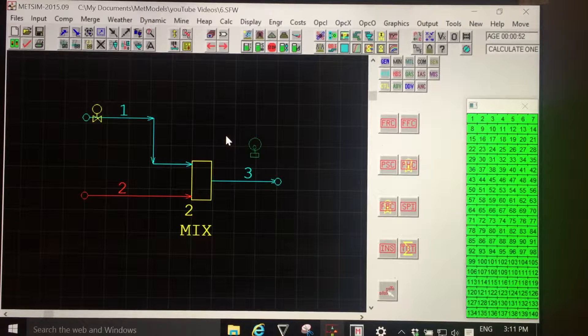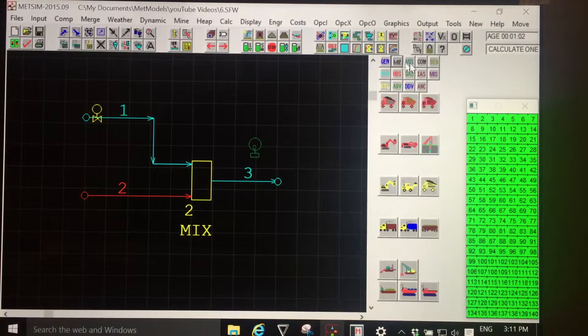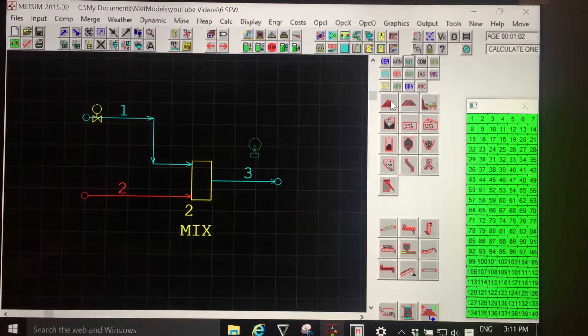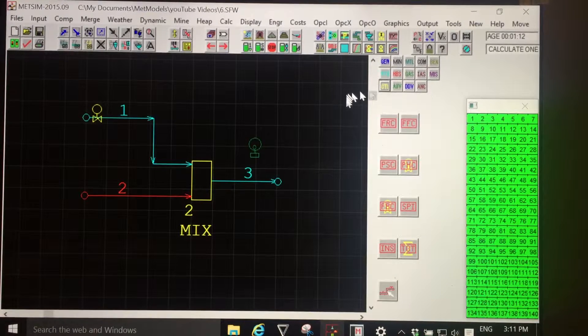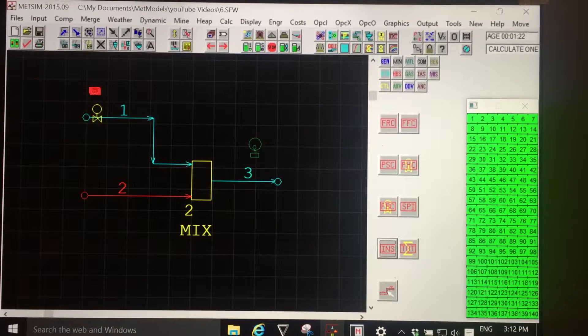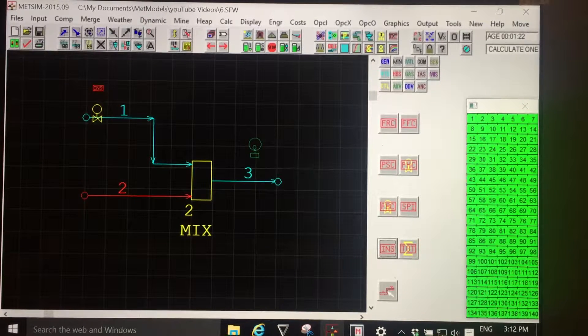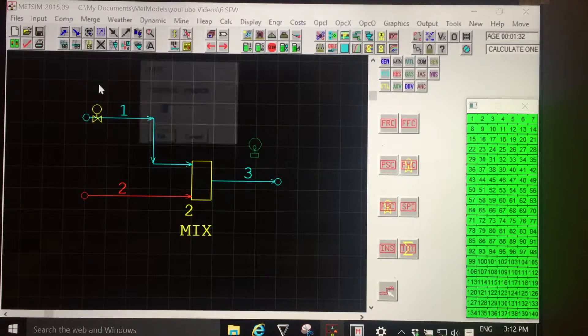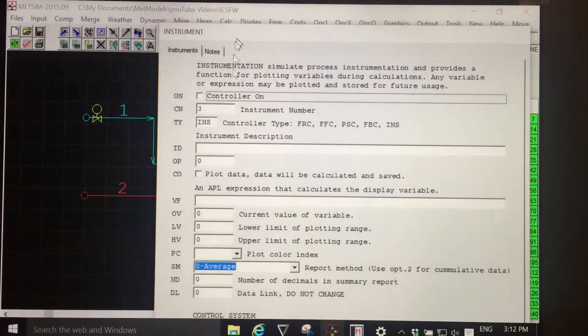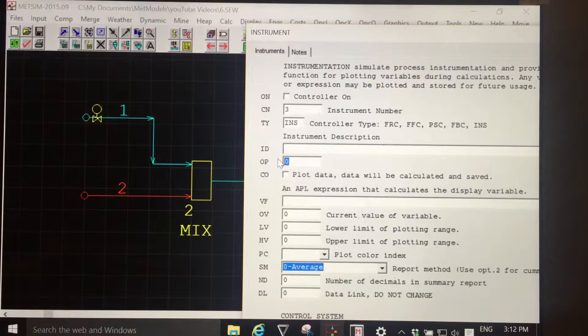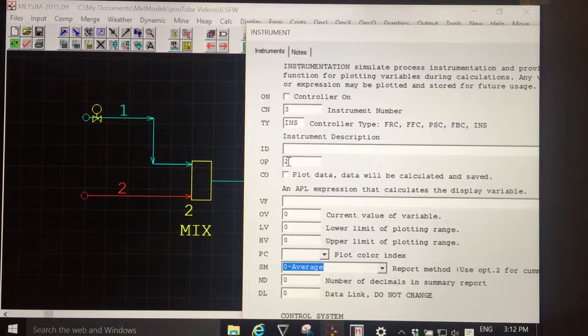I'm going to add another instrument to our simple METSIM model. From the unit operation or models categories, we will choose CTL, and then choose INS for an instrument, and place it on the drawing flowsheet area, above the flow rate controller, because I'm going to use this instrument as an input point for setting the set point of our flow rate control.